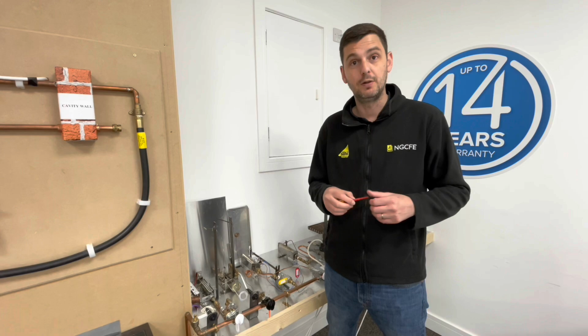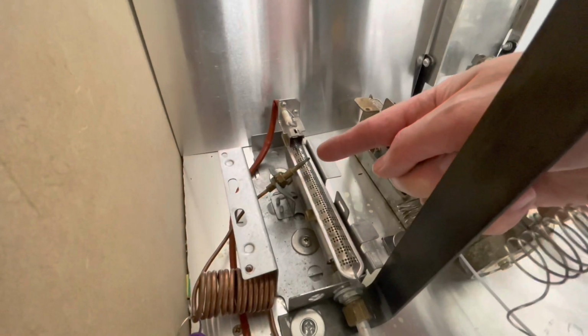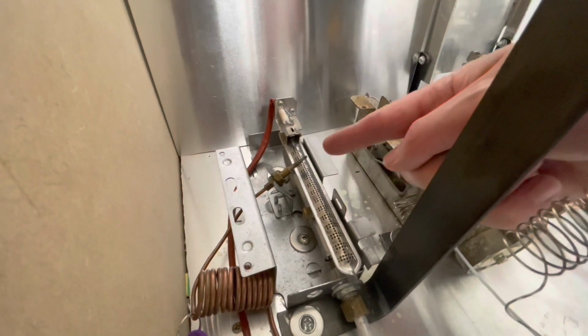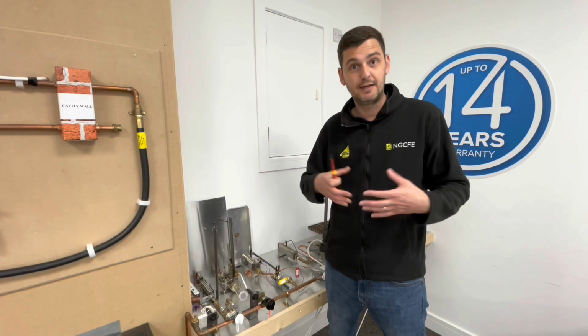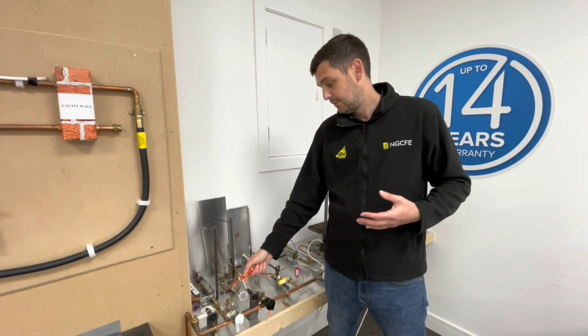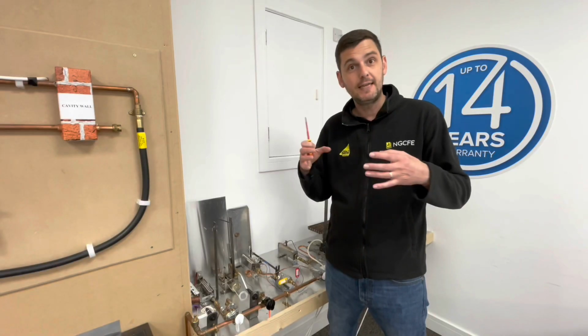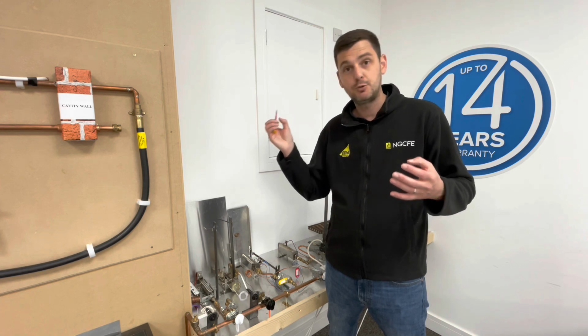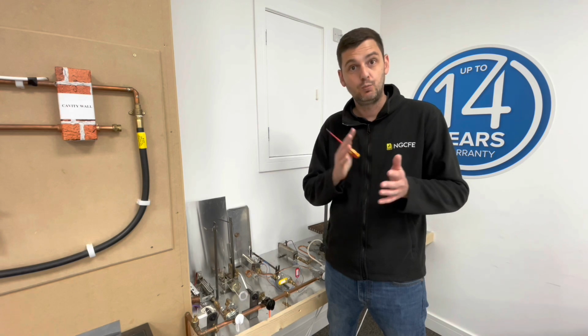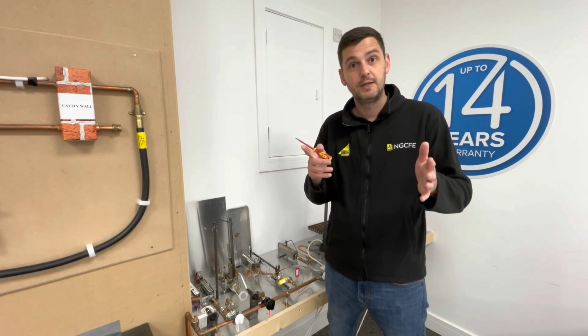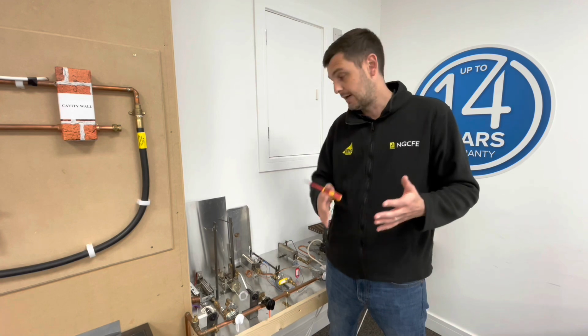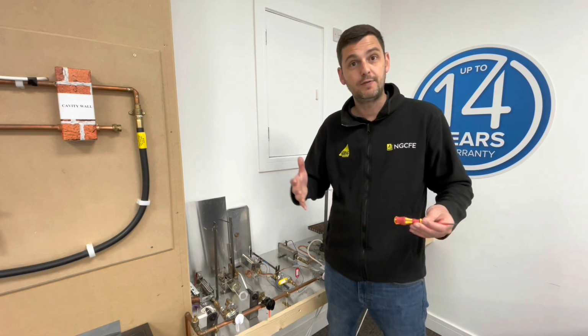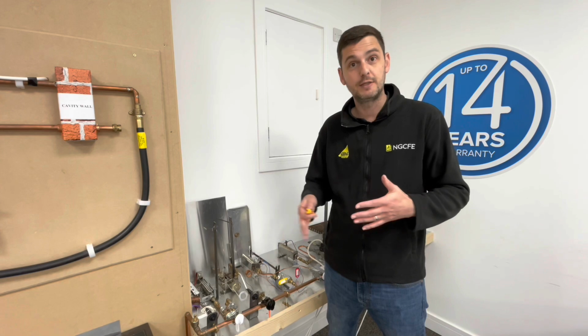So because it's a thermoelectric valve, we know we've got a thermocouple there. So we have a thermocouple, which when it heats up, will keep the burner on at its full rate. We've got a phial at the top of the oven, which when it heats up, will cause the vapor to expand down the capillary tube and close a set of bellows in the valve, which will then only allow a bypass through. So what we're going to do now is fire the control up, and we're going to talk about it as it's actually happening.